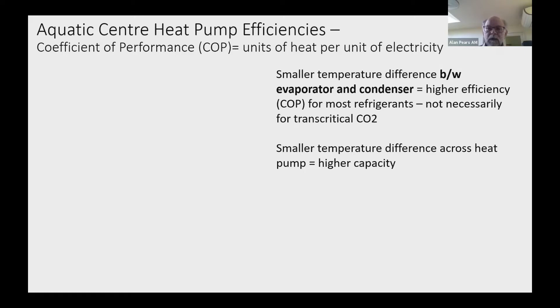The heat pump's performance varies. It's very sensitive to the temperature difference again across which it's working. And this graph shows us how efficient a heat pump can be. And if you look at the grey line at the top, it says COP Carnot. That is the theoretical efficiency of a heat pump operating across a temperature difference as shown on the horizontal bar. So in other words, if a theoretically perfect heat pump is operating across a 60-degree temperature difference, its coefficient of performance is right at the top of that graph, it's a coefficient of performance of 7. That's 700% efficient. Of course, real heat pumps aren't that efficient. They're about half of that.